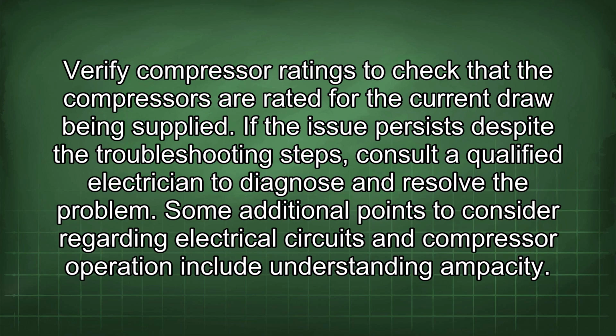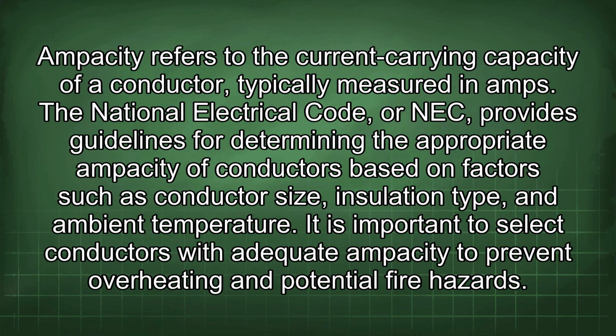Some additional points to consider regarding electrical circuits and compressor operation include understanding ampacity. Ampacity refers to the current carrying capacity of a conductor, typically measured in amps. The National Electrical Code, or NEC, provides guidelines for determining the appropriate ampacity of conductors based on factors such as conductor size, insulation type, and ambient temperature. It is important to select conductors with adequate ampacity to prevent overheating and potential fire hazards.